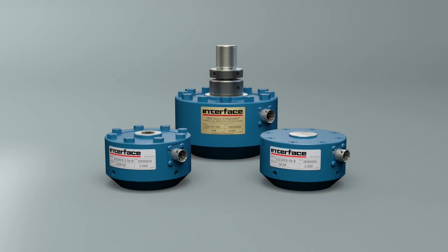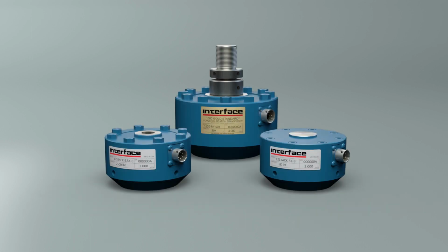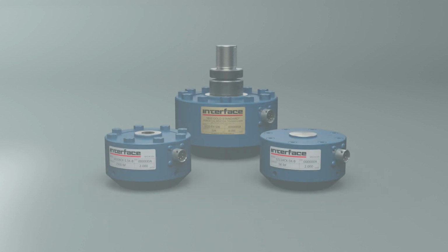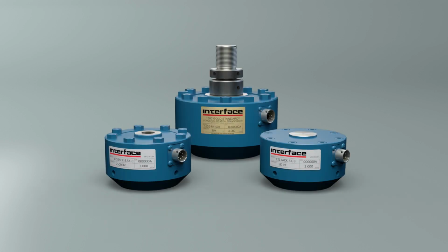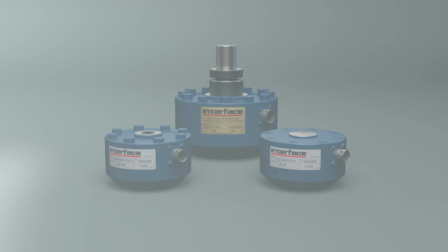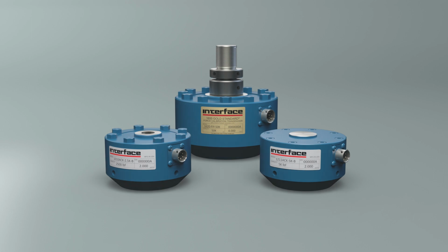Interface is able to produce load cells with a creep specification of plus or minus 0.025% of load in 20 minutes, a factor of 10 better than the uncompensated flexure material. On special order, creep performance of plus or minus 0.010% of load can be achieved. An interesting facet of creep compensation is that, in any production lot, the compensated creep of each load cell can be positive, negative, or even zero. This happens because the gauge creep can be slightly smaller than, slightly larger than, or exactly equal to the flexure creep, within the specification limits.